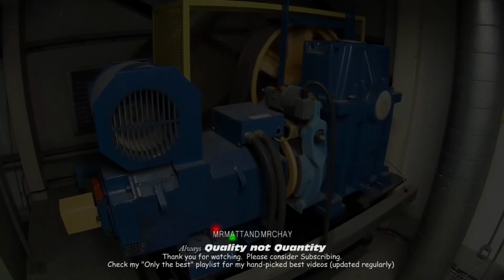The variable frequency drive, that's what runs the motor. Do you know about all this? Car pushed for level 2, car pushed level 3, 4, 5, 6 upwards. That's a landing up button on floor 1, 2, 3, 4. Landing down button, 2, 3, 4 upwards. So they're all inputs into the system. Then these contactors here will be probably for the doors and things like that. Here you go. Open contactor, close contactor.